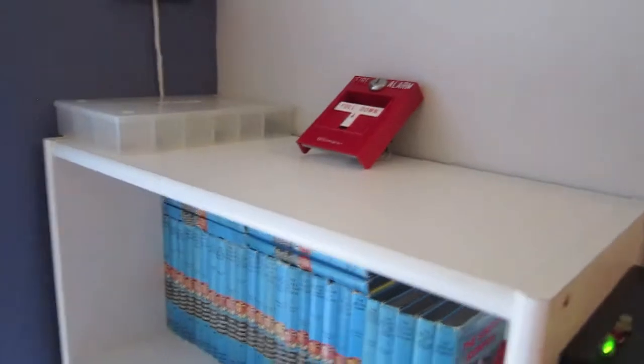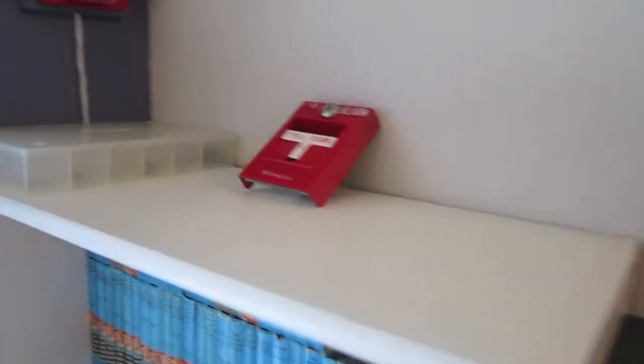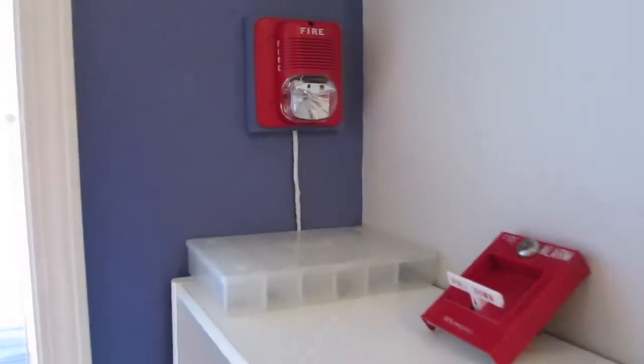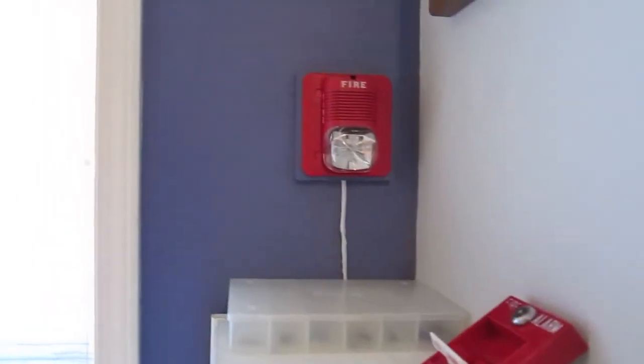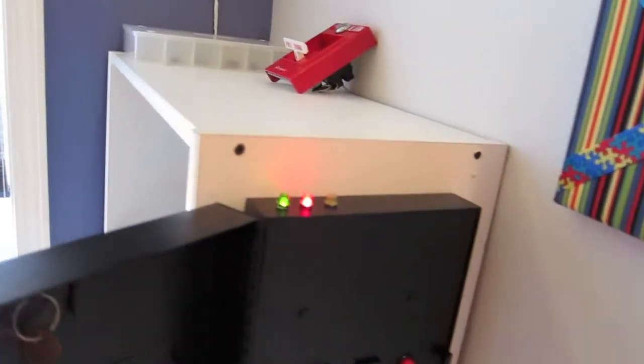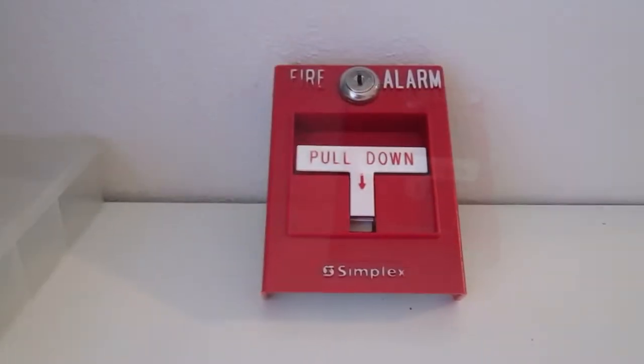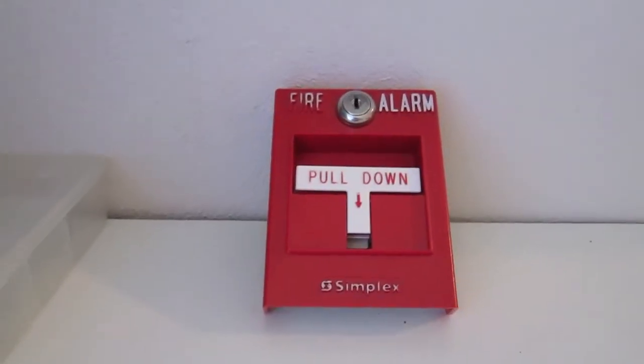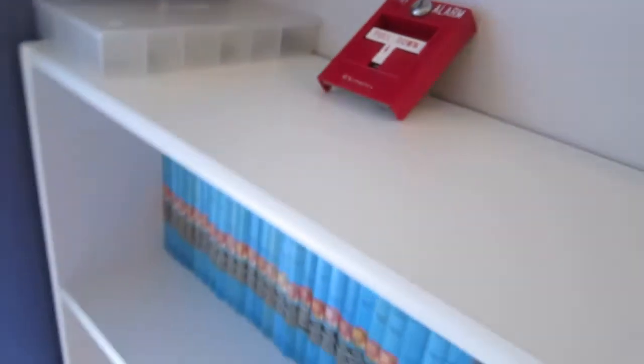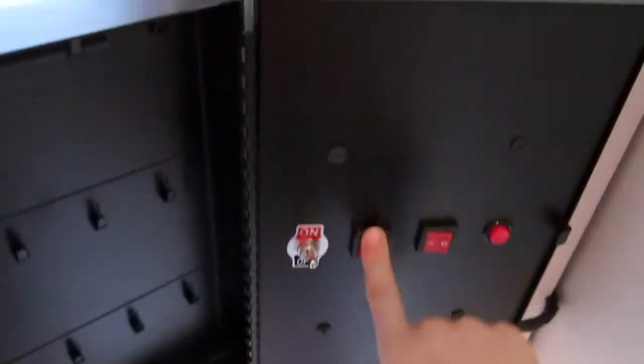Next I'm going to be pulling the Simplex. So I'm just going to go silence it right after I pull it. So I silenced it. The alarm light is on, and now I'm going to reset the Simplex. Now I got the pull station reset and I can go back to the panel and silence it.